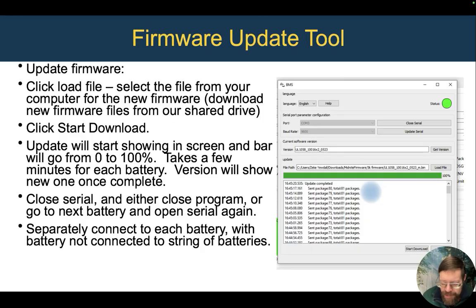If you do this, you'll have to shut all the batteries down and then turn them on one by one as you connect to them. And then when you're done, shut them all back down, reconnect the battery comm cables, and turn the master battery back on, which will turn the whole bank back on.